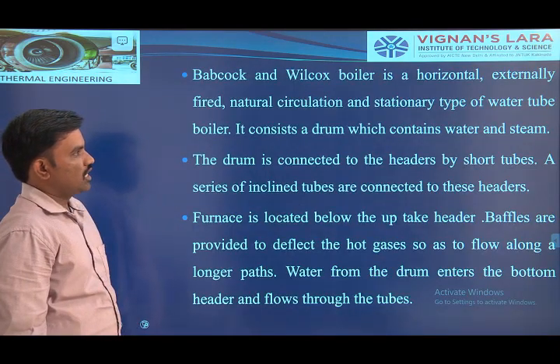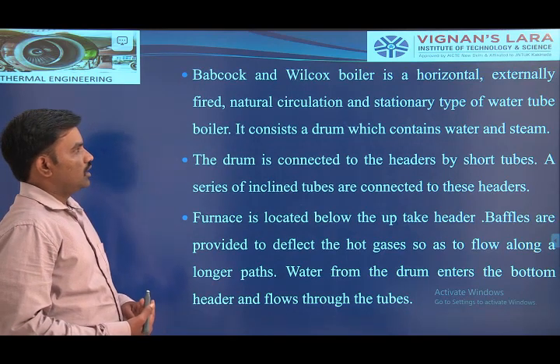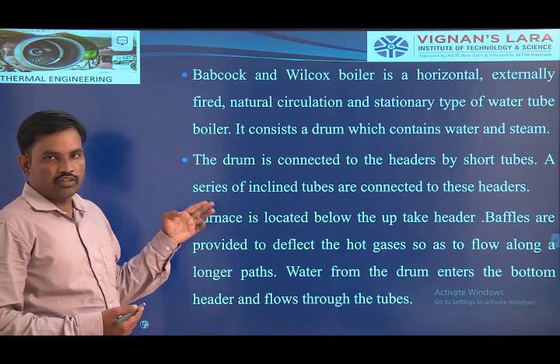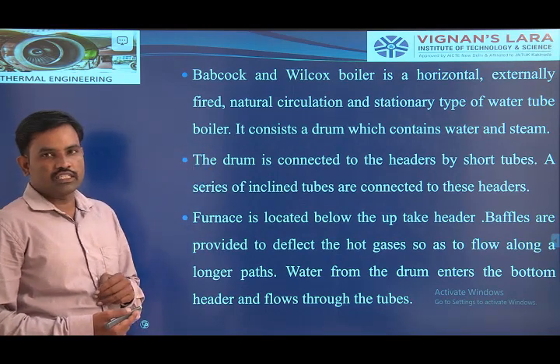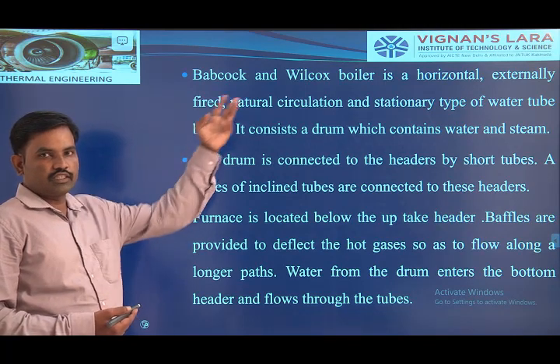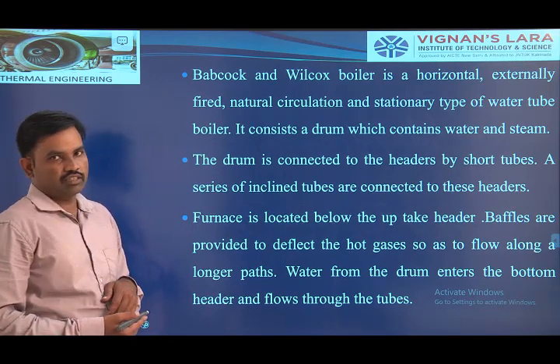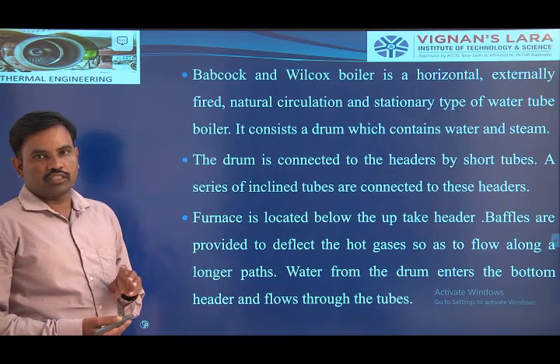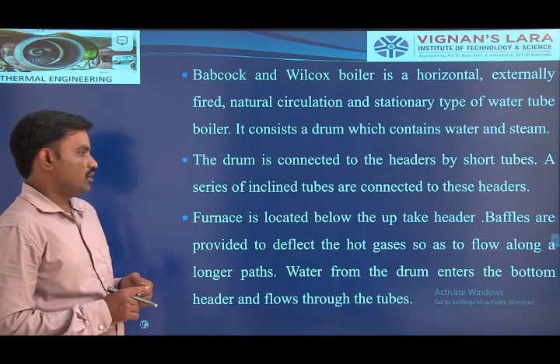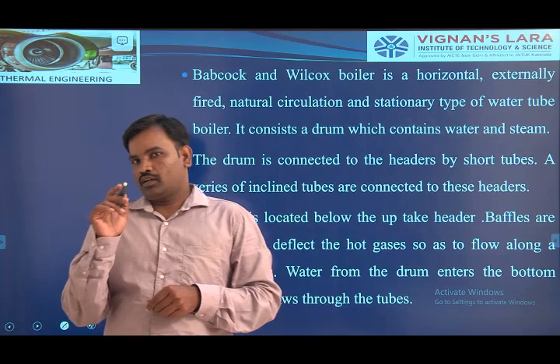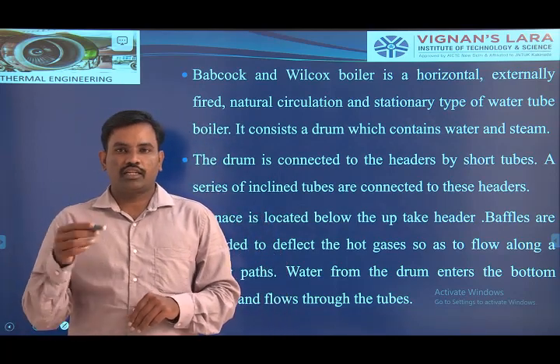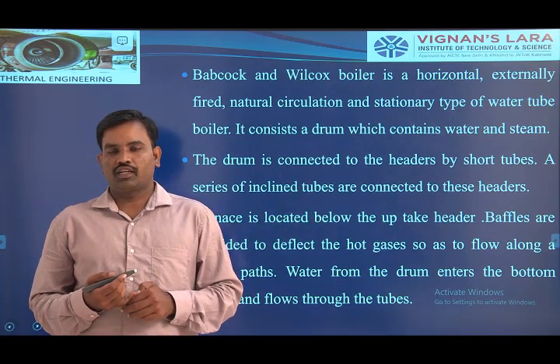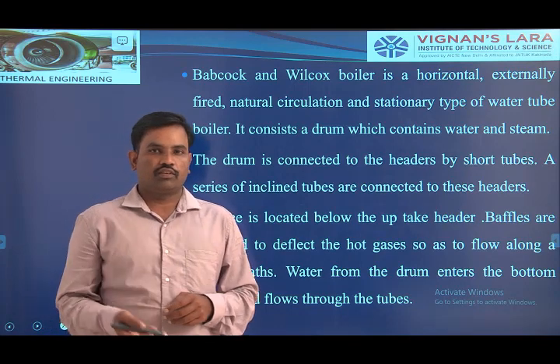The Babcock and Wilcox boiler is a horizontal, externally fired, natural circulation, stationary type of water tube boiler. The water flows inside the tubes, and circulation is natural due to gravity difference only. Hot flue gases are generated inside the combustion chamber and introduced into the boiler section. The drum is connected to the upper and lower headers, through which we introduce the feed water. With the help of baffle plates, we are increasing the heat transfer time between the flowing gases and the water — we can increase the heat transfer rate from the hot flowing gases to the feed water.